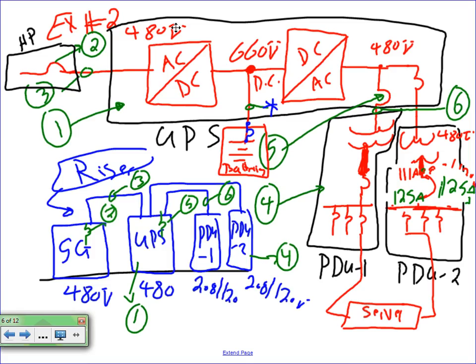Cool? So the whole idea, guys, is that if the power goes down right here at the high voltage panel, this will not see any interruption of power because it's tied to 2 sources of power, a DC source and an AC source. And it's tied right here, tied all the time. You don't have to parallel. They're already tied at the DC level.